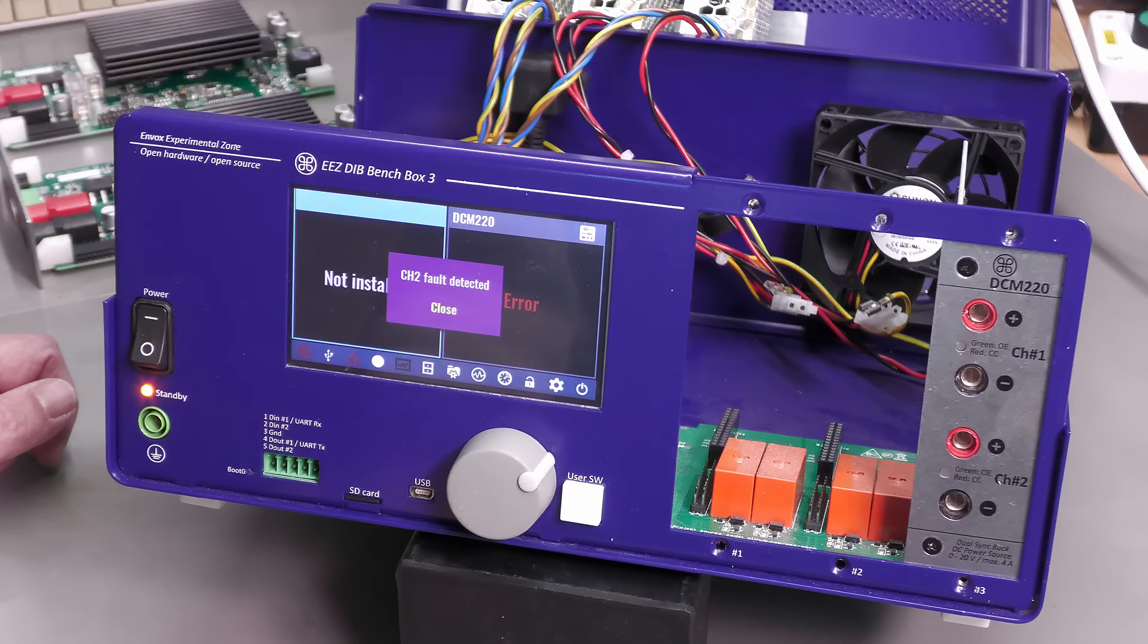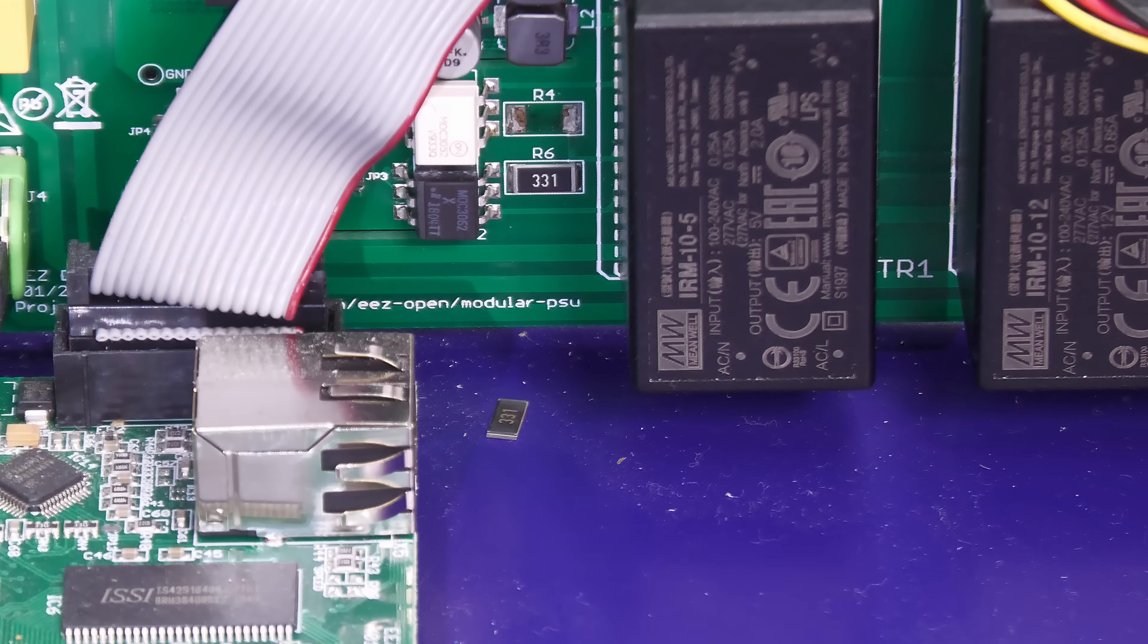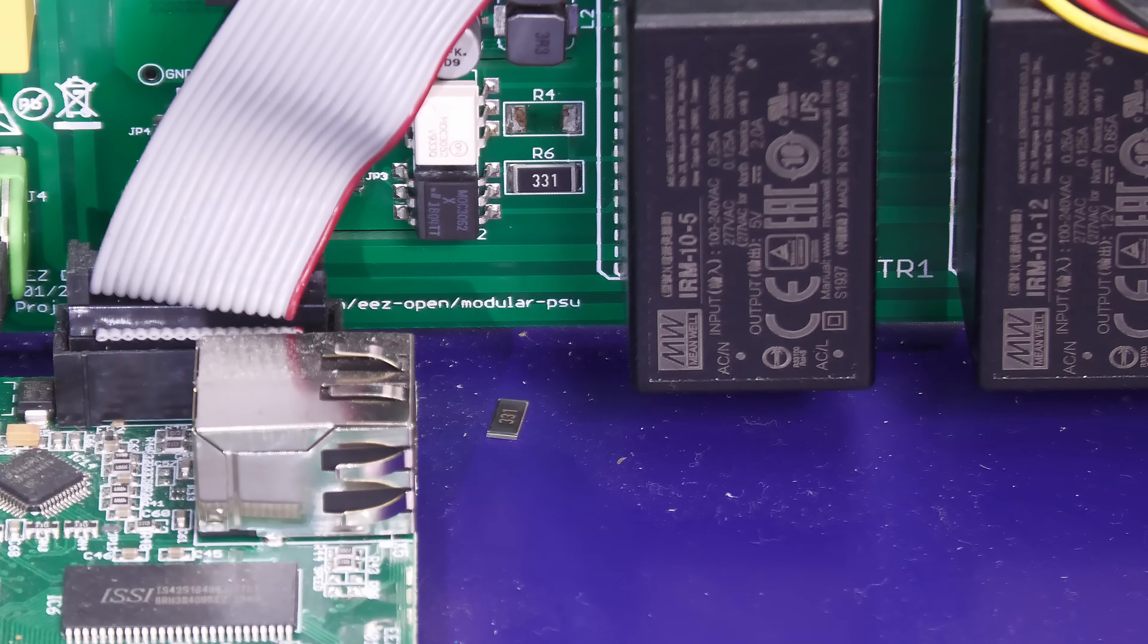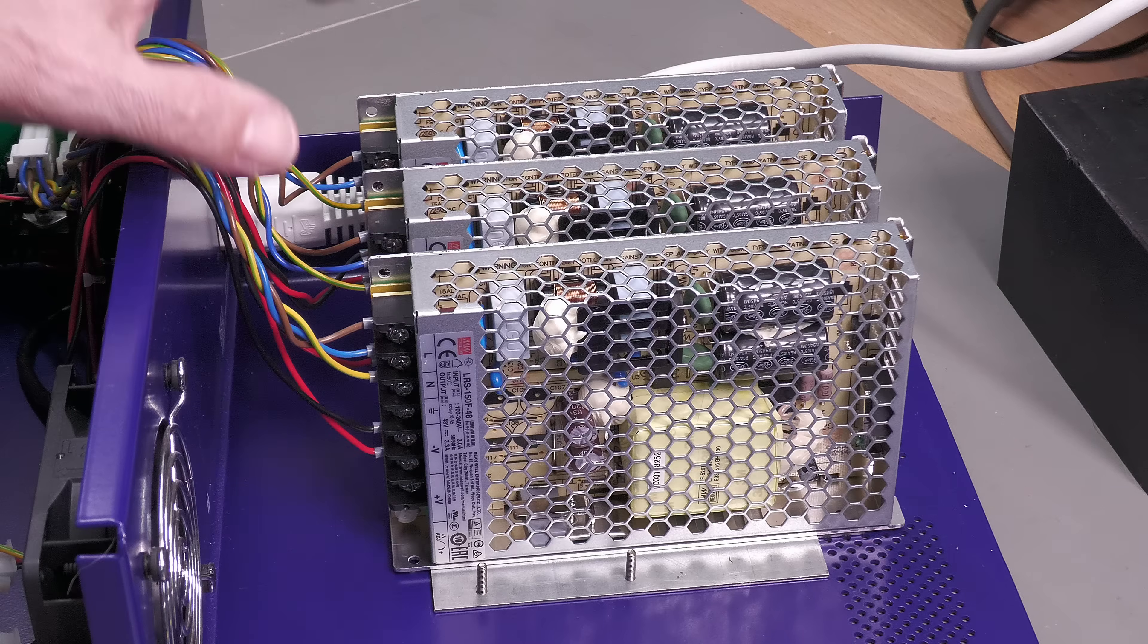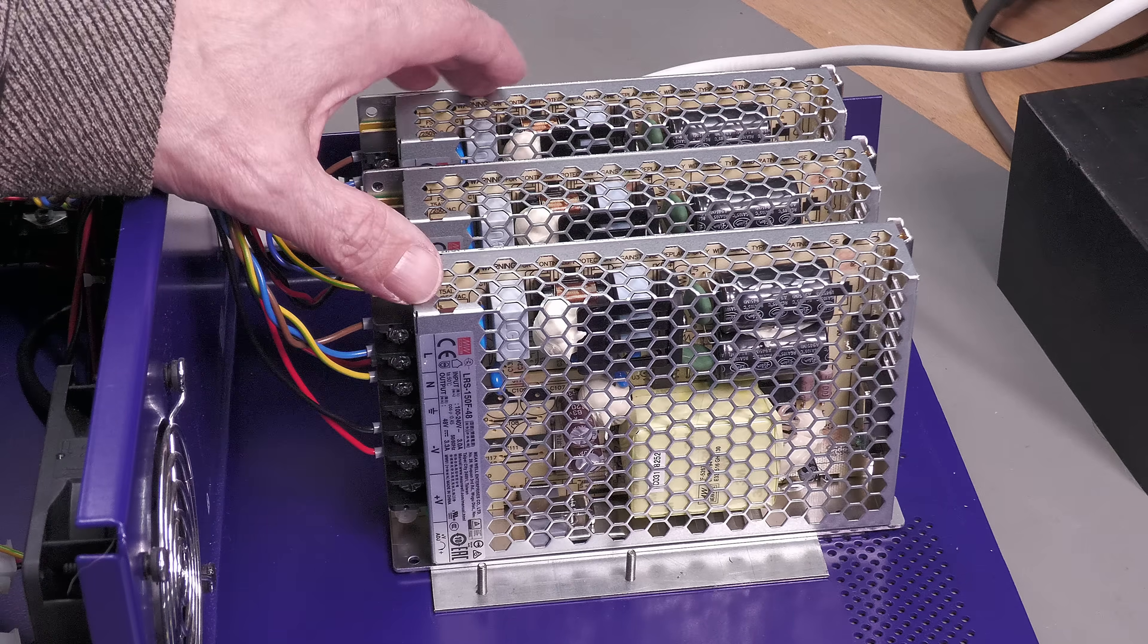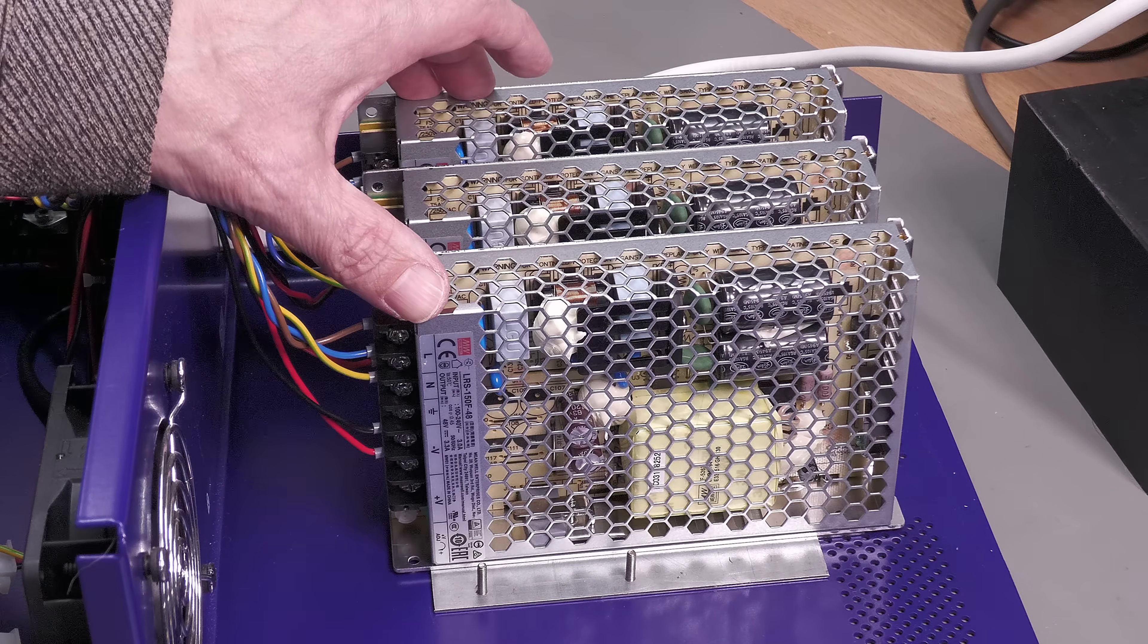This is what I was greeted with when I opened up the unit and looked at the auxiliary power supply board. This is the circuit board that interfaces to the three Mean Well power supplies that deliver 48 volts to the system. The fix is to install a snubber across the live and neutral to one of the power supplies, and apparently that stops the overheating of R4.